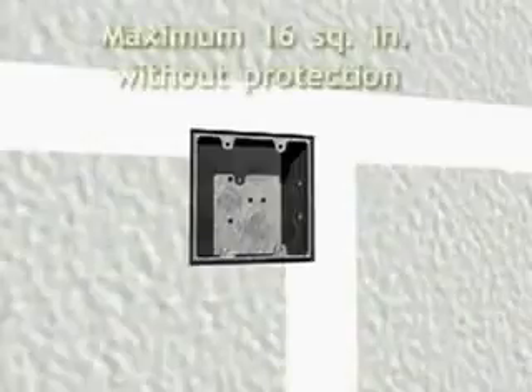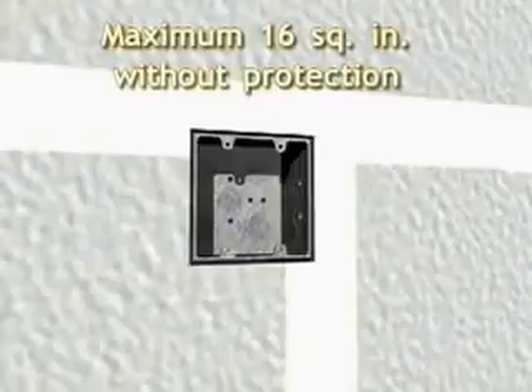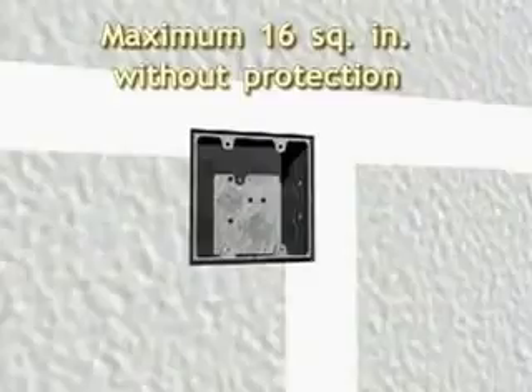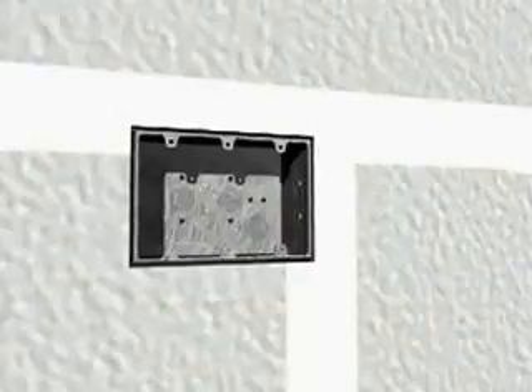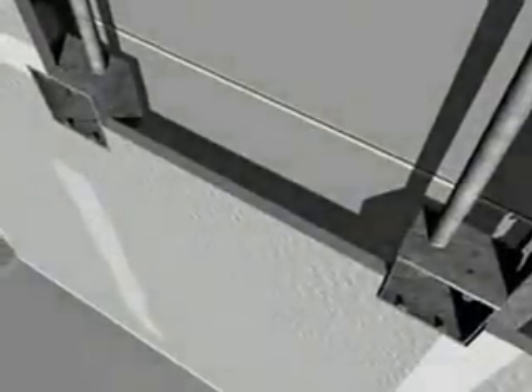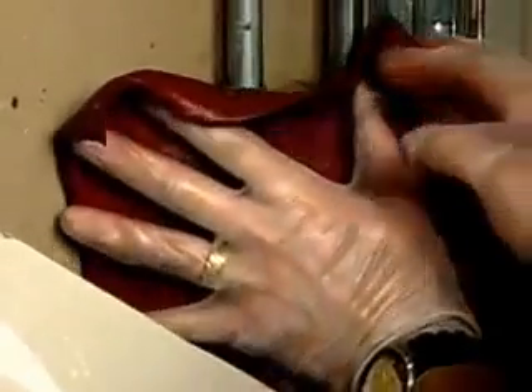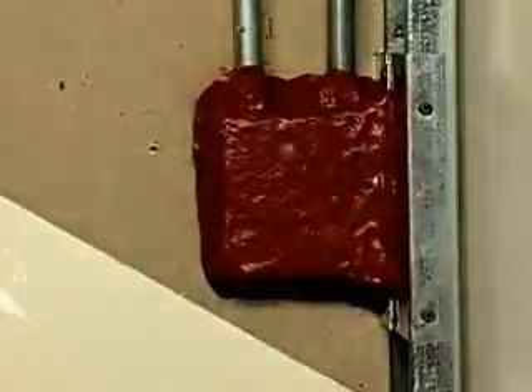Codes permit an opening for these boxes of up to a maximum of 16 square inches without protection. This presents a problem when the 16 square inch limit is exceeded with a larger box, a combination of multiple boxes within a single stud cavity, or boxes on opposing membranes. When these conditions are encountered, the boxes must be protected with Firestop putty pads.